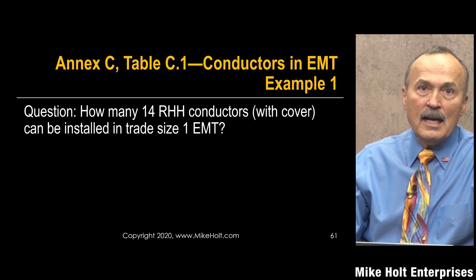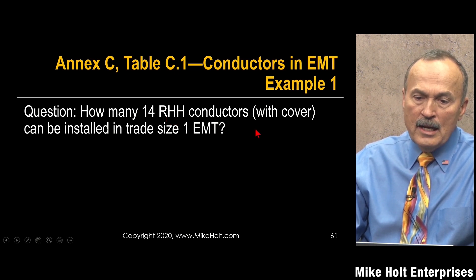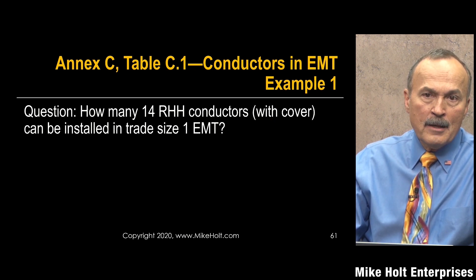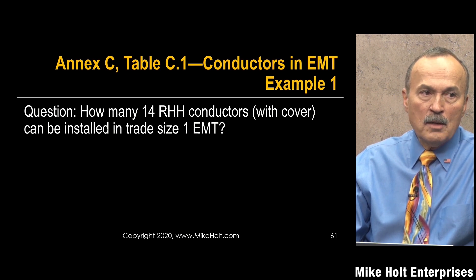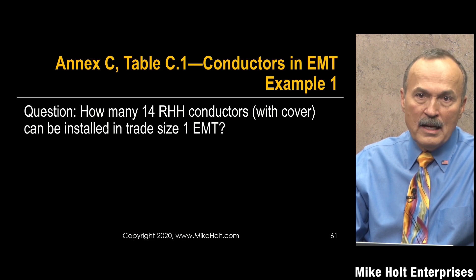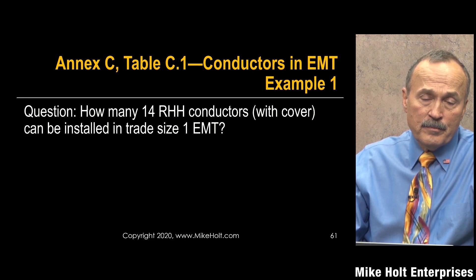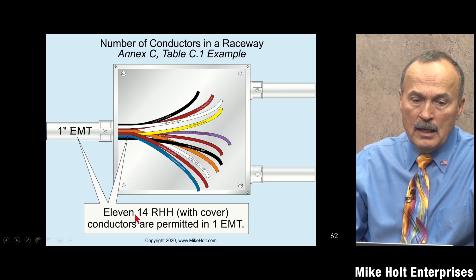Let's work an example with Annex C. This is Table C.1 - EMT with 14 AWG RHH with cover. That combination doesn't really make sense today - you won't find RHH conductors going into an EMT raceway with cover, that was old Romex - but it's a question so we answer it. Going to Annex C.1, RHH with cover, the answer is 11 conductors.